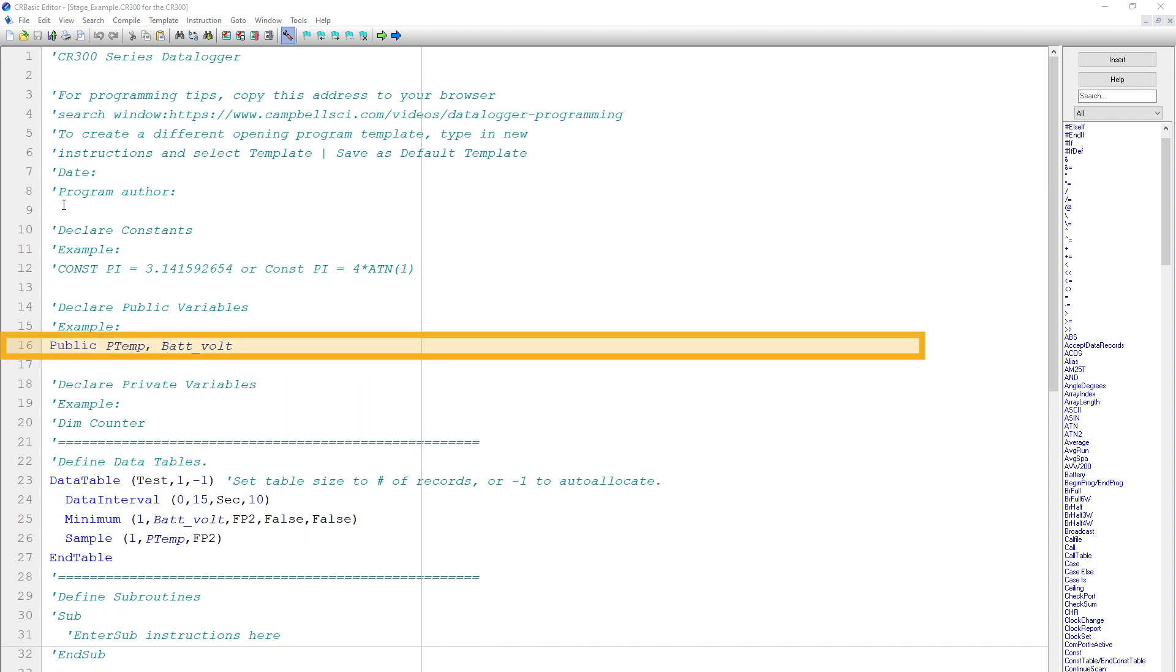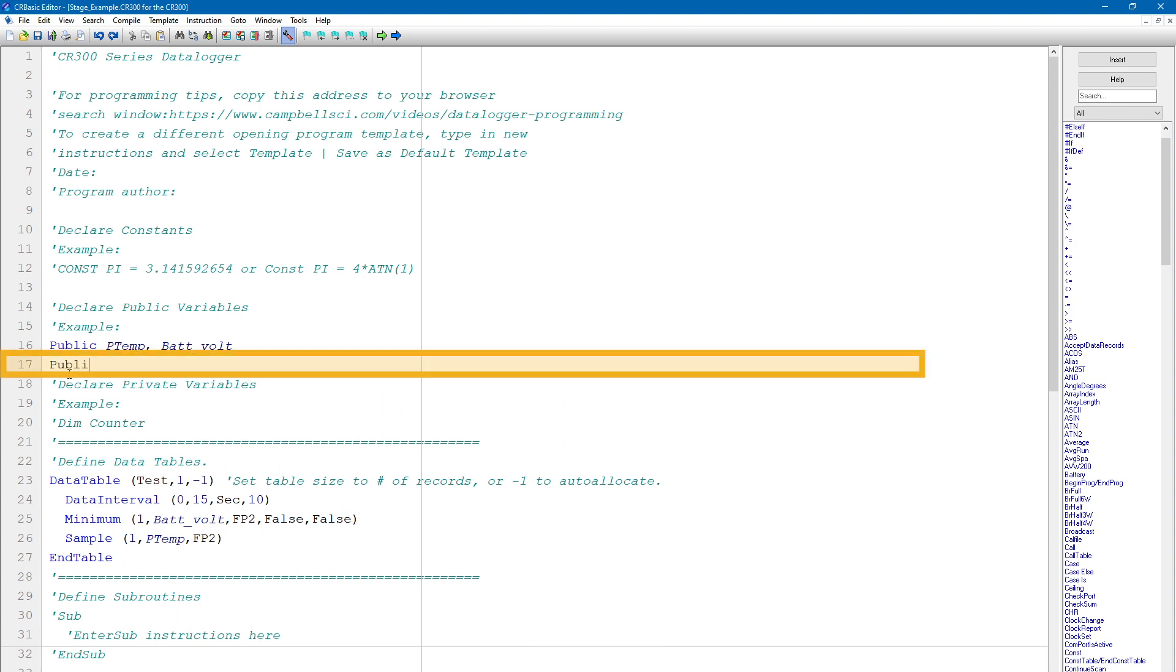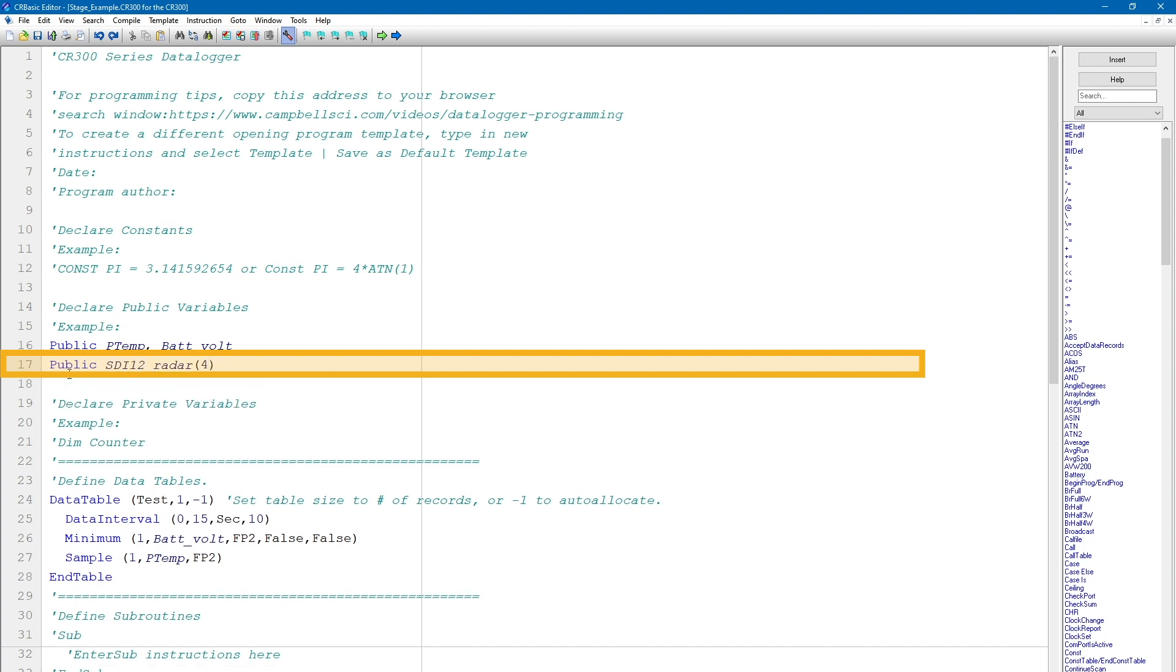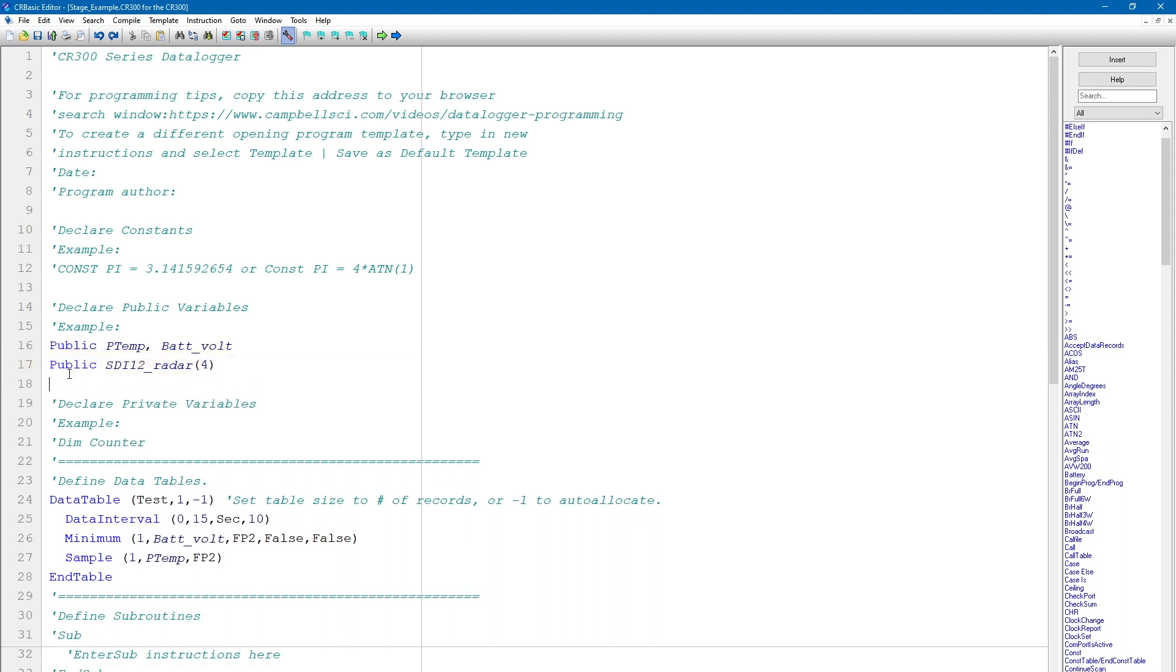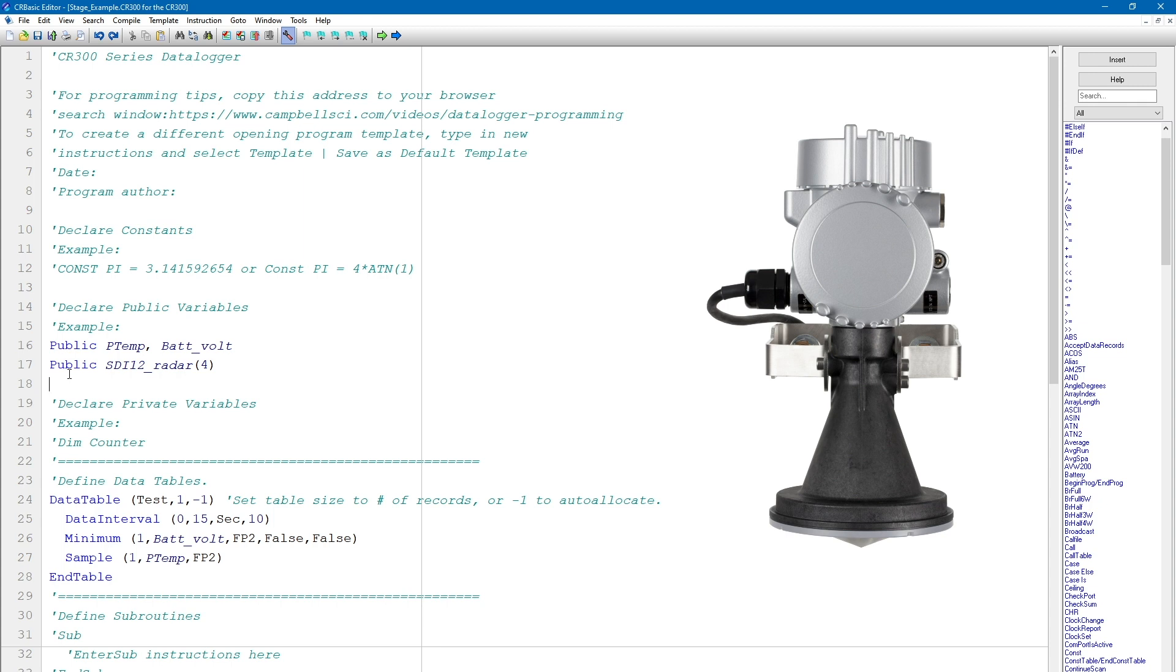My program already has some variables declared. In this video, I will add an SDI 12 stage measurement to the program. I begin by adding a public variable named SDI 12 Radar 4. I'm making this variable an array of 4 because the sensor I'm using is a CS475A Radar Gauge from Campbell Scientific, which outputs 4 measurements.